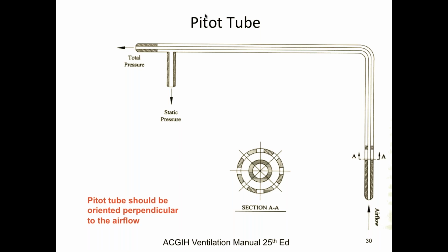So that pressure that you feel in there, if you cover the end of that hose, is static pressure. There's no air moving, it's standing still. That's the pressure that's in that hose or that ductwork when the air's standing still, and so it's called static pressure. That static pressure will determine how much air you can pull through there, how much velocity you can pull through there. Static pressure is the same in all directions. Once you cover that, air's not moving. The static pressure acts the same way in every direction. It's a negative pressure because it's sucking. And if you put a hole on the bottom, it would pull air in, because it doesn't matter what part of the ductwork you're on. Static pressure is always the same in every direction.